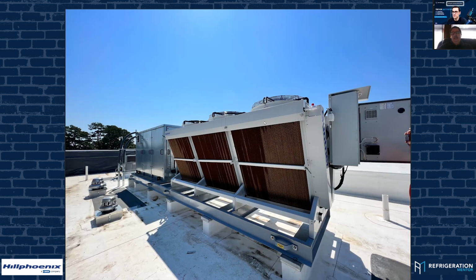And then in the winter, when you're minus 20 out, you stand the chance of steaming any moisture that might be on that coil, because the fans aren't running, and that moisture likes to waft up to the volutes and the fan blades and freeze there, and then freeze the fans in place. And we had this happen a lot. That caused a lot of alarms, and we did a couple other things to take care of those. But on the Güntner, if it goes to start and it doesn't sense movement, it senses high amperage, it'll jitter the fan back and forth to try to break it loose.